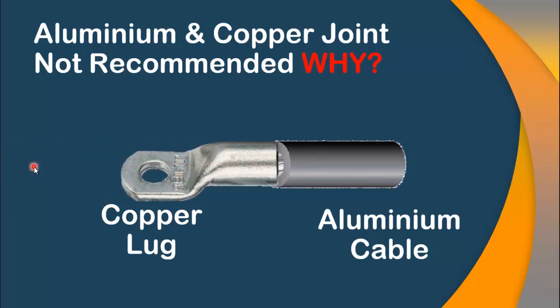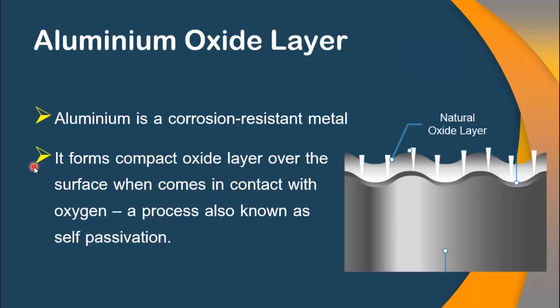So this joint is highly not recommended. In this video, I will tell you the reasons why copper and aluminum joint is not recommended in the electrical world. Let me discuss the most important property of aluminum, which is the formation of aluminum oxide. Aluminum forms a compact oxide layer over its surface when it comes in contact with oxygen, and this process is called self-passivation.